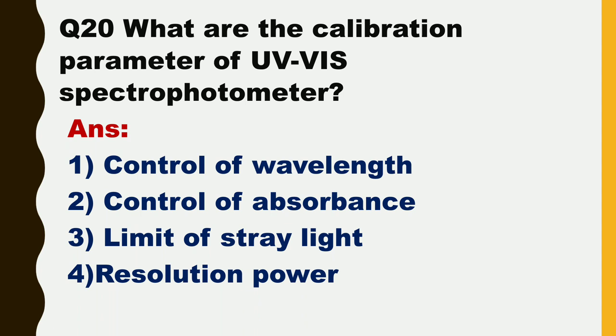The last question is: what are the calibration parameters of UV visible spectrophotometer? The following parameters are used to calibrate the spectrophotometer. These are: control of wavelength, control of absorbance, limit of stray light, and resolution power.